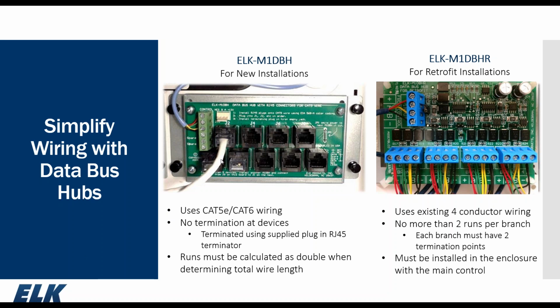Now, we're using 6 of the 8 conductors inside that cable. We're using 2 of those as a return path, one for data A, one for data B, because this hub basically does the daisy chaining for you. So you don't have to worry about doing that in the panel, and you've made a nice, neat, clean installation using the DBH. Each home run must then be calculated as doubled because it incorporates the return path. So now we have a total of a 2,000-foot overall data bus using the DBH.